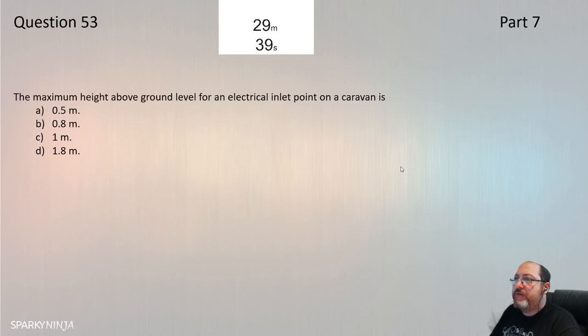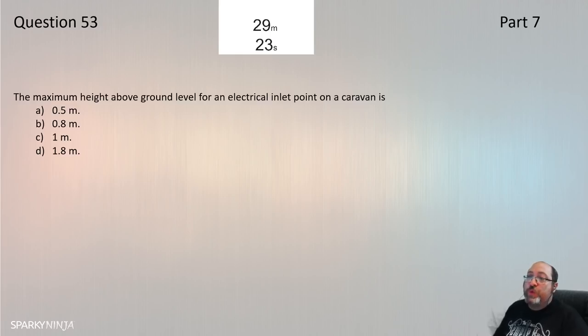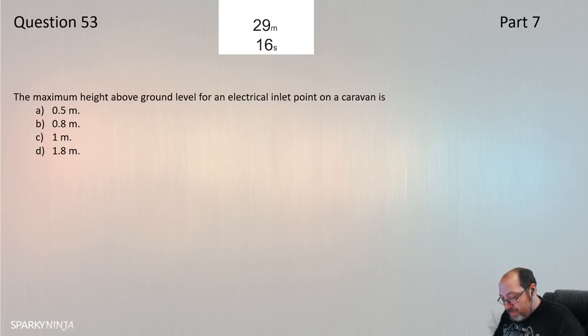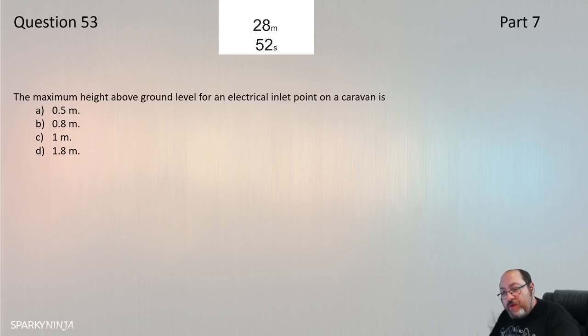Question 53: Maximum height above ground for an electric inlet point on a caravan — regulation 721, not caravan park. Going to 721.55.1.2: the inlet shall be not more than 1.8 metres above ground level. Question 53 is D, from 721.55.1.2.